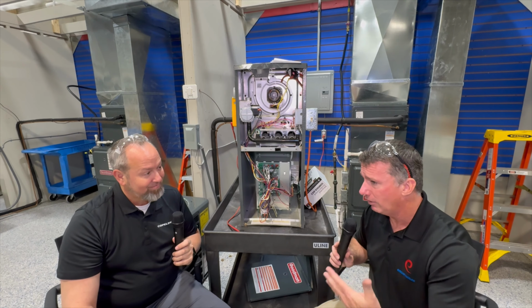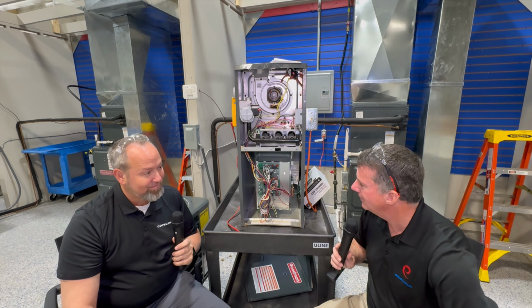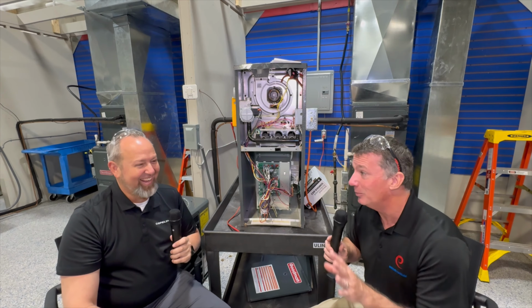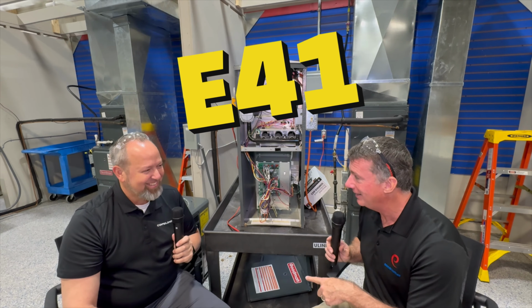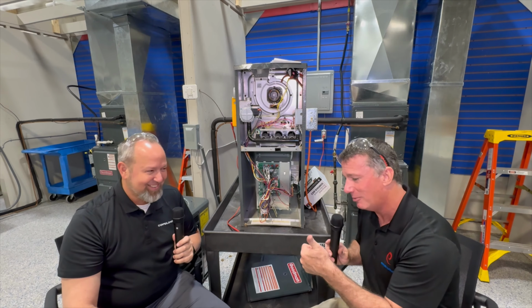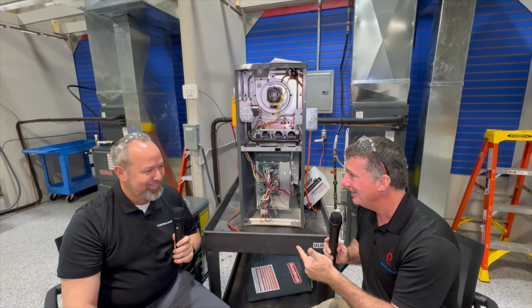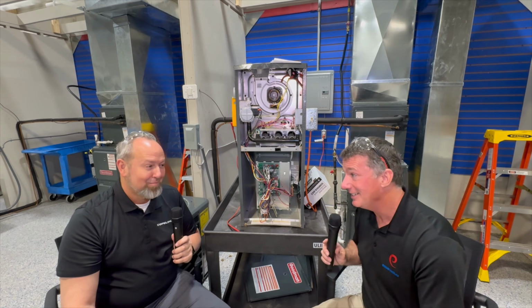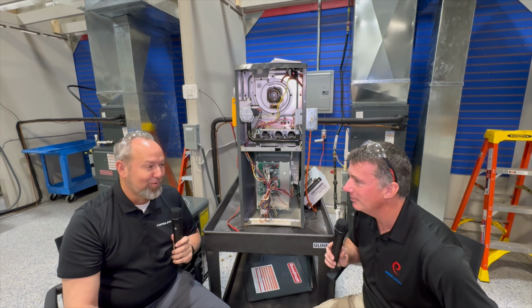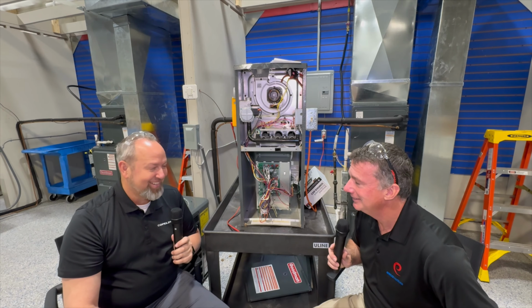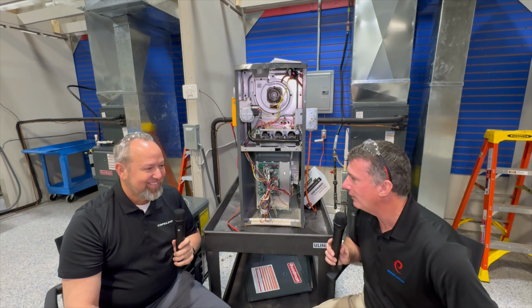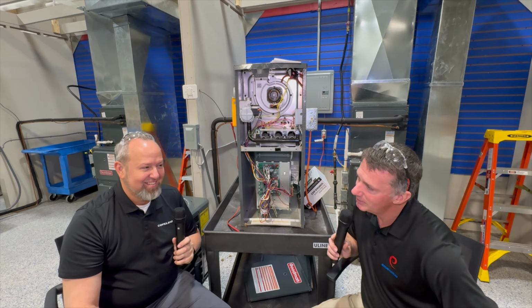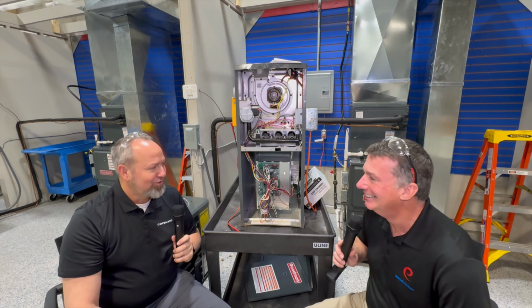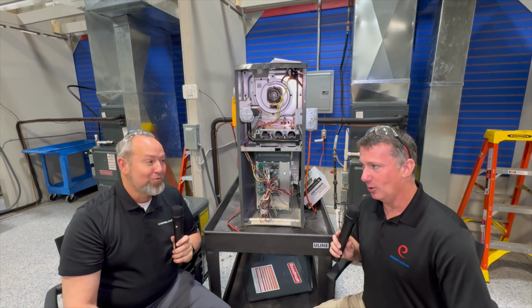So you've got a variety of replacement options, and I'm liking the changes in technology. But if I get an E41 error code when I fire it up, it probably wasn't the board to begin with. It was probably a rollout, an igniter, or pressure switch. Pressure switch is almost number one, the most common of all of them. Yeah, it is, so it's a good educational tool. You fire it up and you get an E41, better get back to the basics. Don't just say, oh no, I got another bad board.